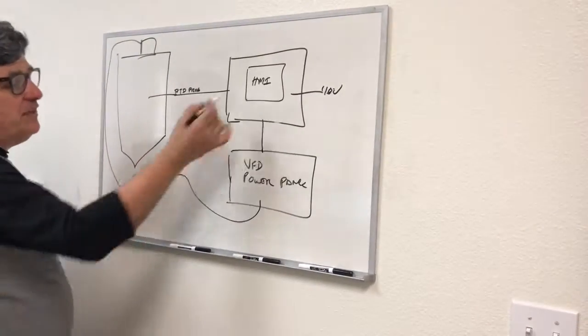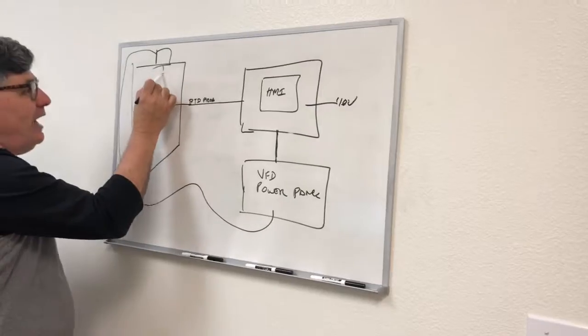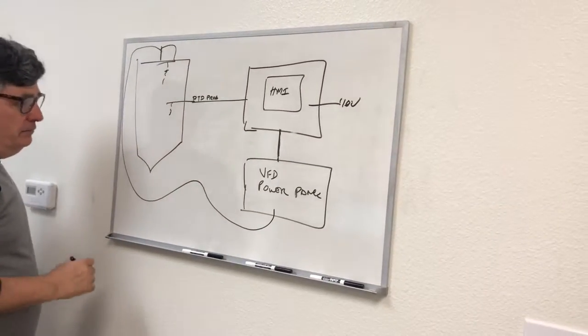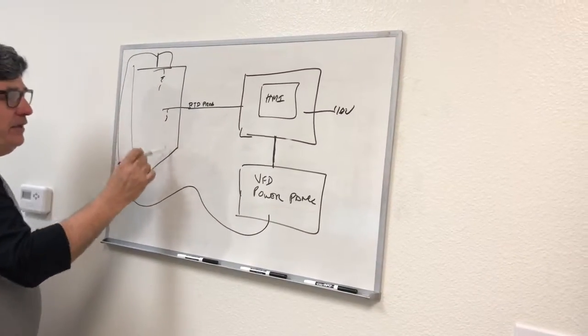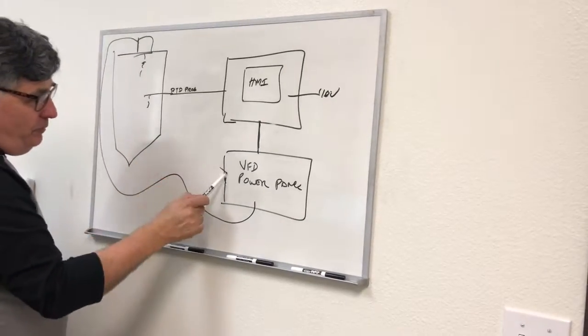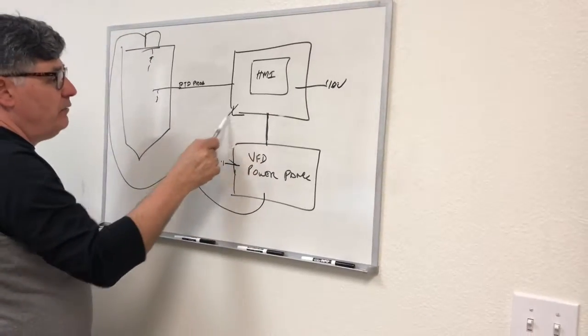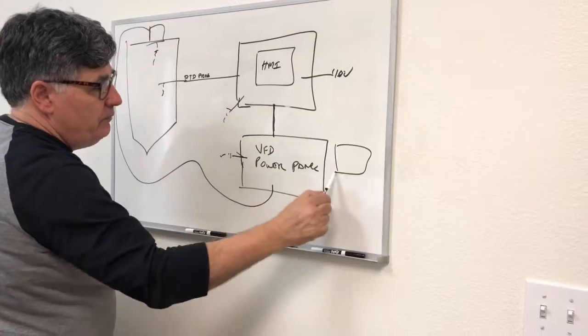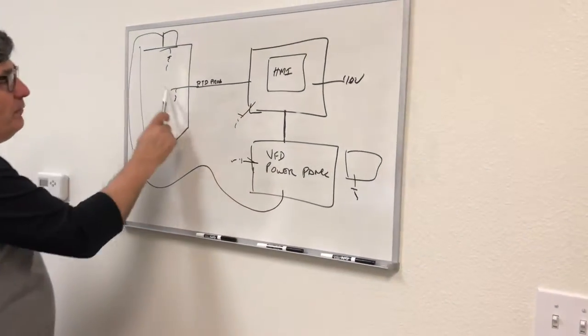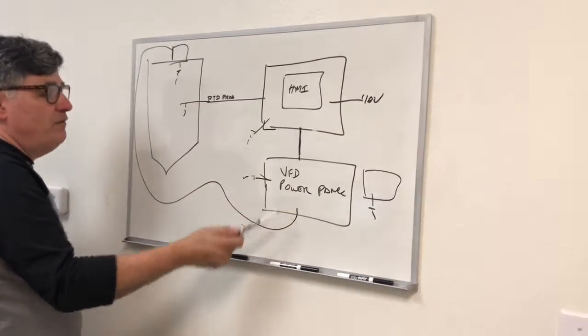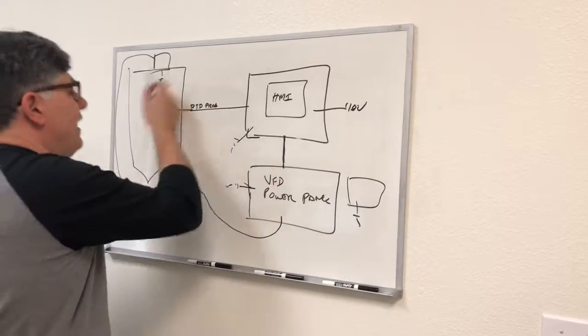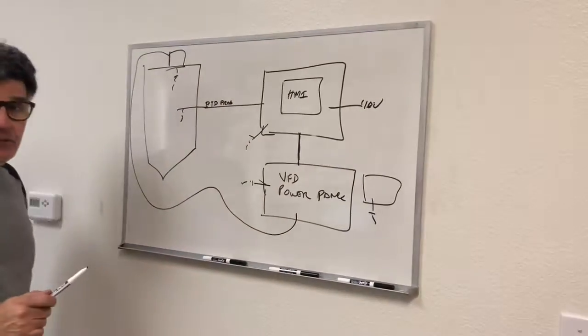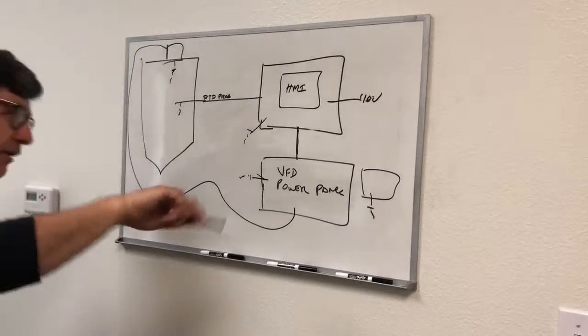They still have interference, even if you isolate them this far, because that common ground, that grounding that's necessary, always leads back to the panel, because there's a ground in this panel, and there's a ground in the HMI, and there's a ground in the main power panel feed. So even if we isolate these two panels, the fact that there is a common ground wire that connects everything is the issue. Now, can we fix it? Can we get around it?